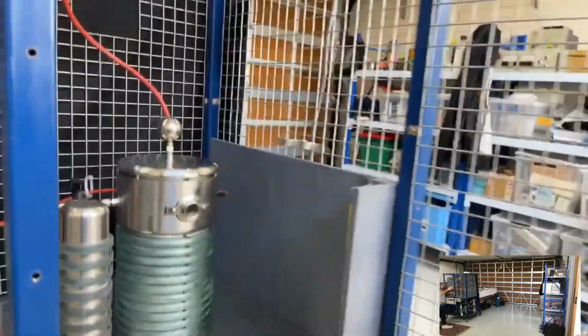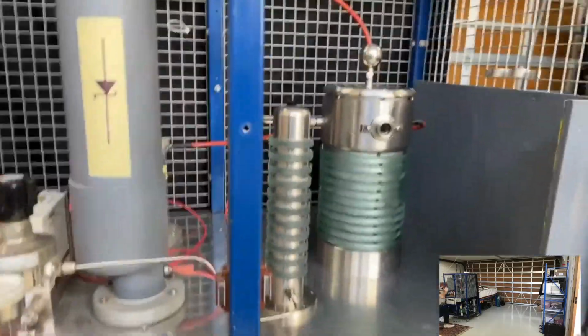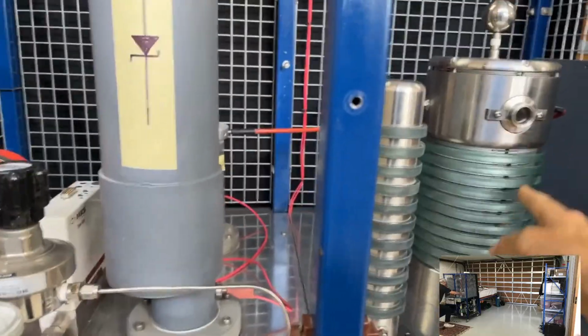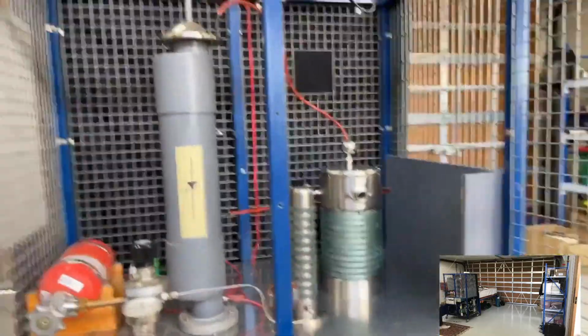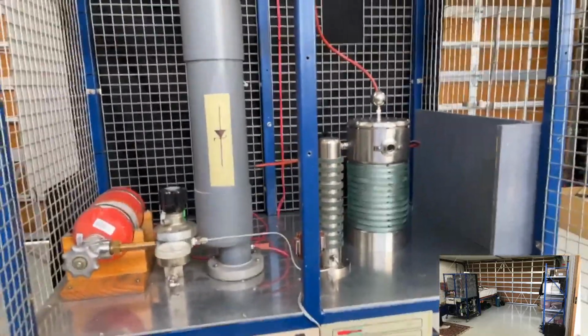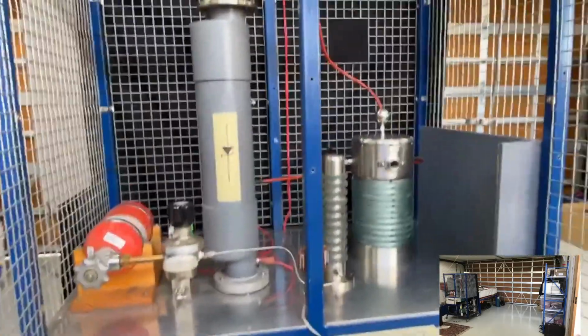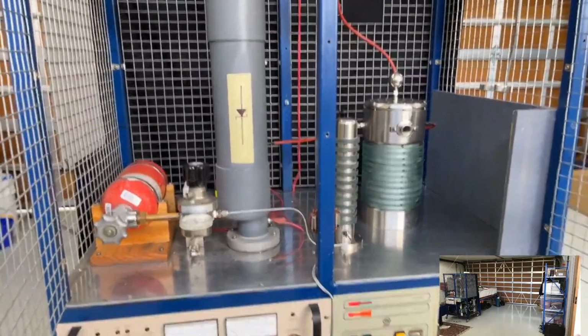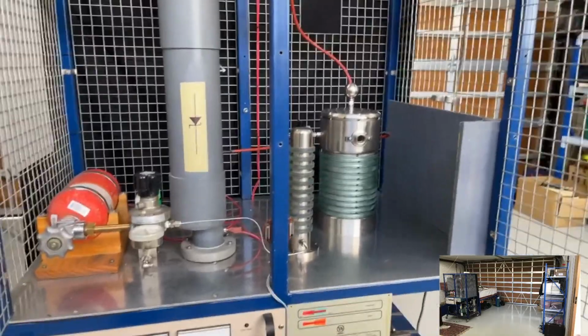an extra little lead shield here on the side, which shields that area over there where I sit, because the only area where X-rays can come out is along these glass discs, because we're using ordinary float glass and not the lead glass.